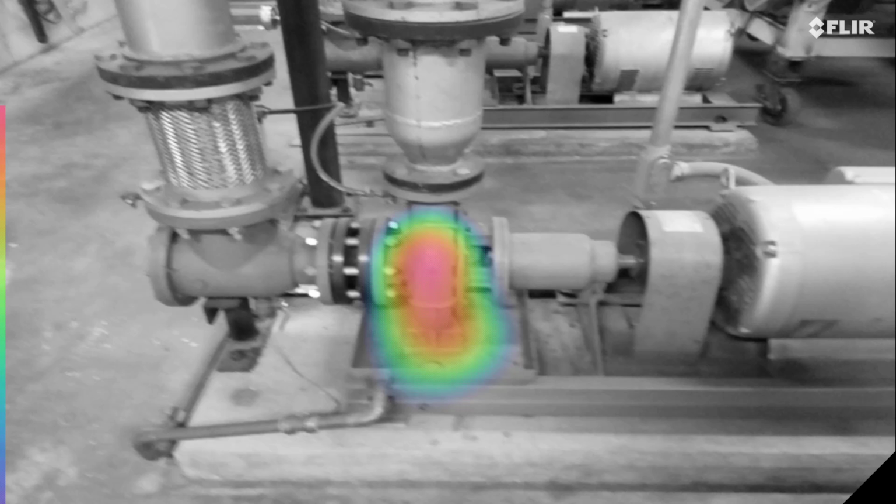So here we have an image of a pump. This basically just shows there are other types of leaks that can be detected beyond partial discharge or compressed air, etc. Right? Looks like there's a sound coming from that particular spot, and the different colors allow us to determine where that sound is coming from.